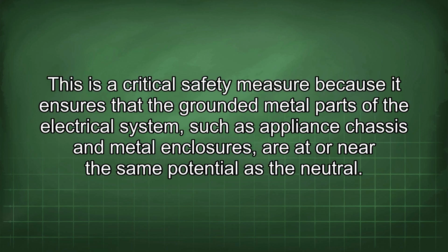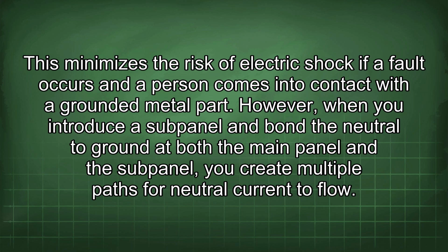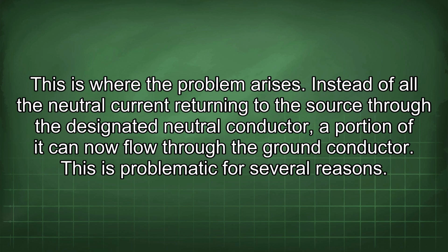This is a critical safety measure because it ensures that the grounded metal parts of the electrical system, such as appliance chassis and metal enclosures, are at or near the same potential as the neutral. This minimizes the risk of electric shock if a fault occurs and a person comes into contact with a grounded metal part. However, when you introduce a subpanel and bond a neutral to ground at both the main panel and the subpanel, you create multiple paths for neutral current to flow. This is where the problem arises.